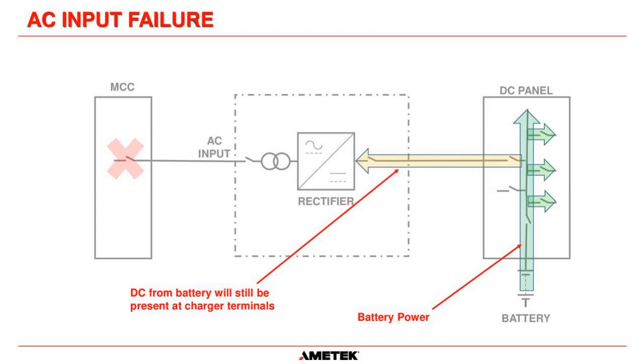So if we have a power failure in our MCC, so 480 volts is lost, then what happens is the battery starts feeding the load circuits without any interruption whatsoever. And there's no switching involved. There's no transferring. It's just like you pulling the AC cable out of your laptop. Your laptop just carries on going regardless. It doesn't switch off and then switch back on again. The DC loads will not see any interruption in the power to them whatsoever.